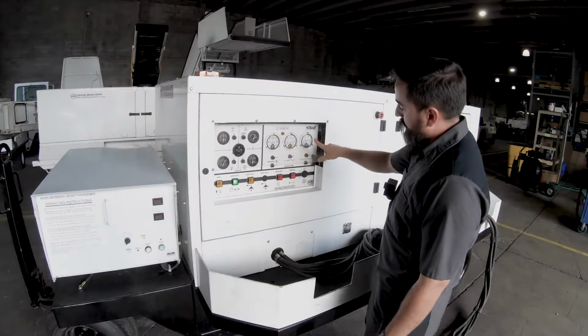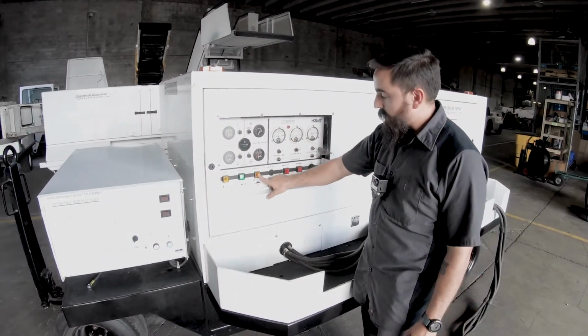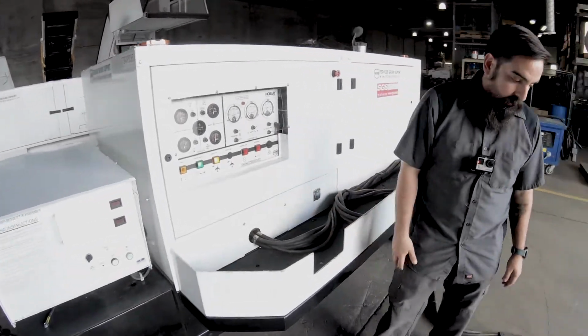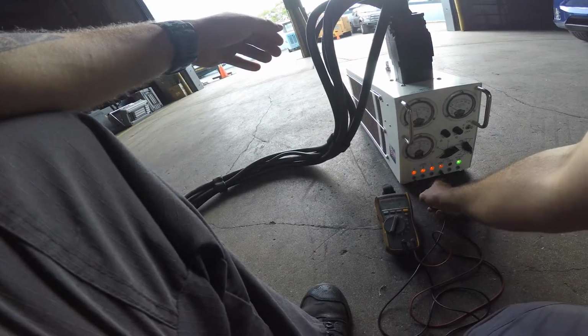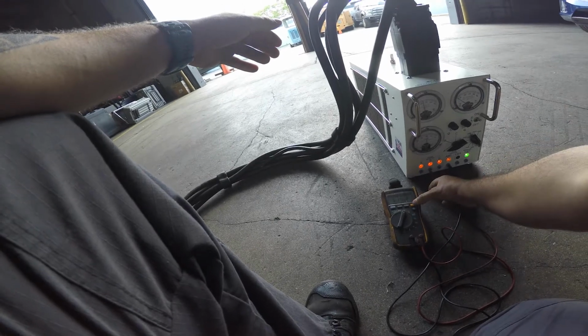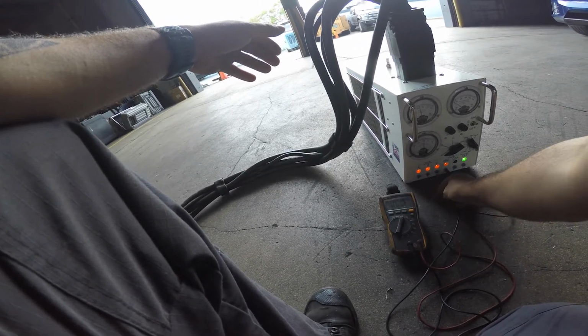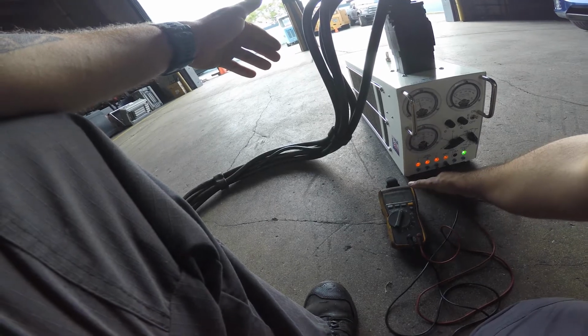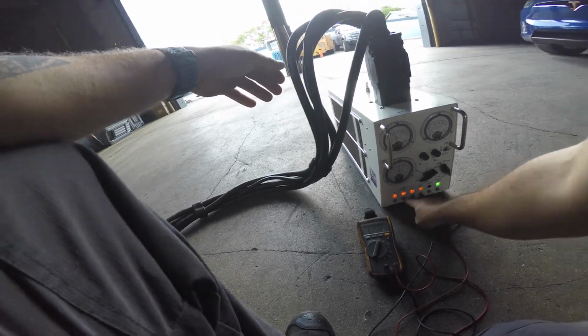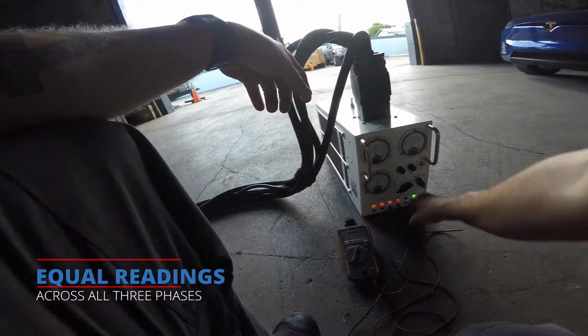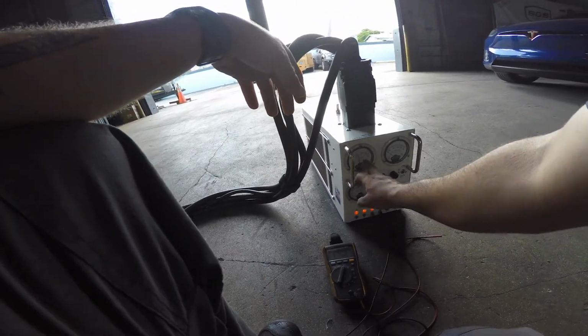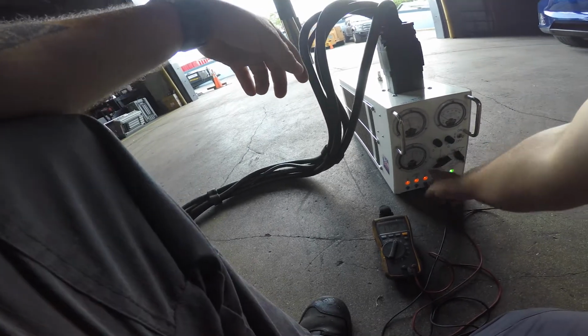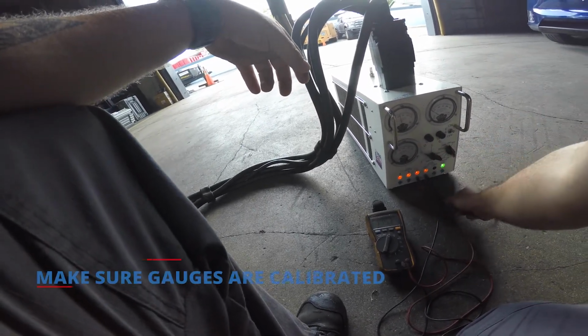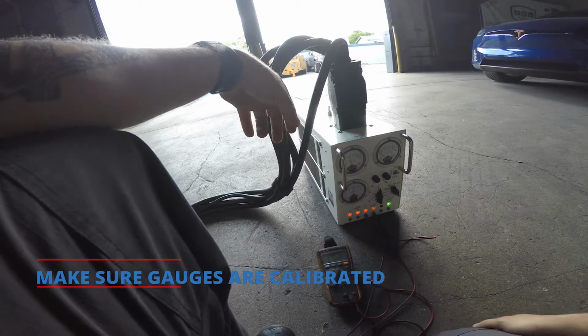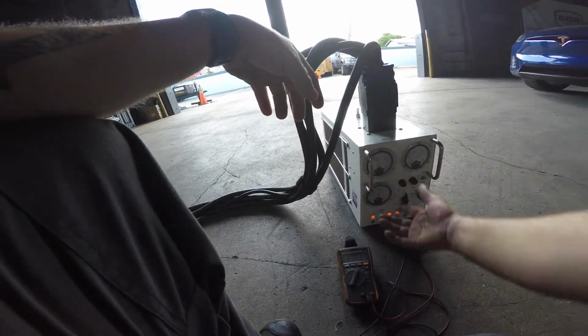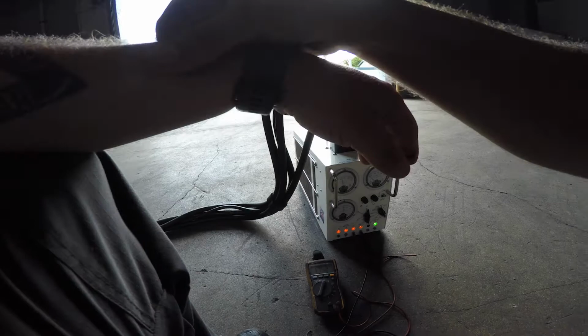Once you have 400 hertz and 115, you can close the contactor. Essentially all three phases give you exactly the same. Now if you don't have a voltmeter, you can check with these gauges. So here you have phase A, phase B, and phase C. They should be reading exactly the same, all three.